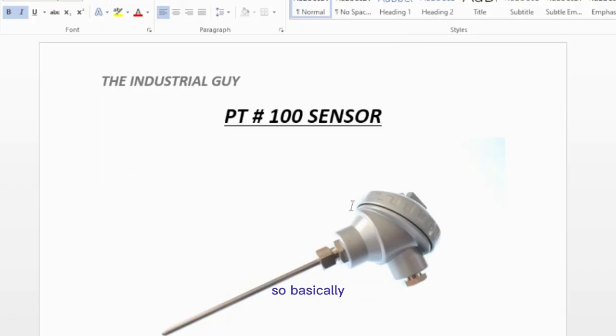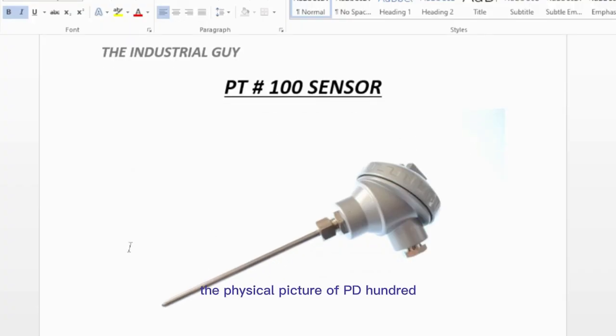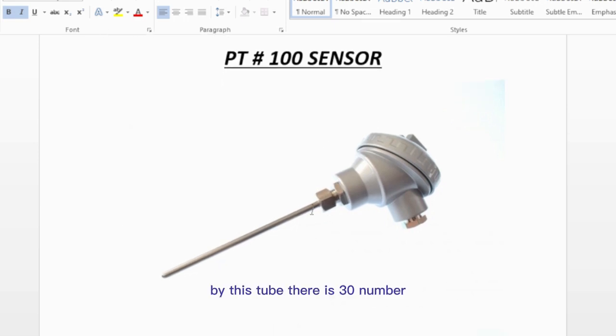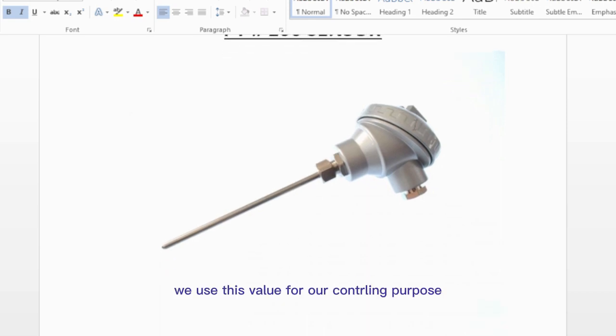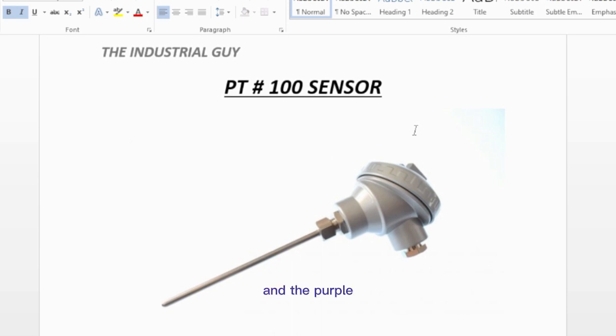So basically, this is the physical picture of PT100. Inside this tube, there is platinum, which is mounted on this side, known as the housing. This is fixed on whatever application requires the temperature. The platinum gives us the value in ohms, which we use for our controlling purpose and other purposes.